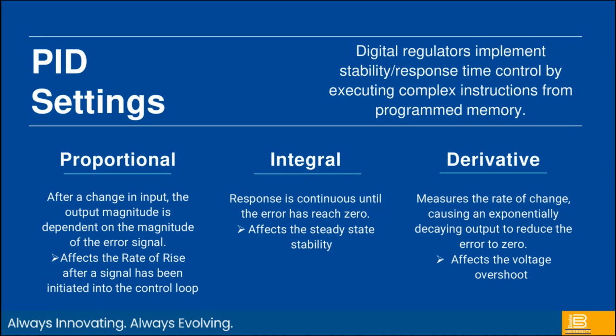So at a high level, when I look at proportional, it's how fast I'm going. So it's my rate of change, how fast I'm driving there. Integral is my steady state stability. After proportional has done the majority of the work, it's kind of getting me there to make sure I'm stable and I'm driving to zero. And derivative is almost looking into the future. So it's looking at how fast I'm moving, and it's going to start correcting based upon the speed I'm going. So it can help with overshoots. So proportional is typically rise time, integral is steady state, derivative is overshoots. So that's kind of at a high level how those gains fit in.